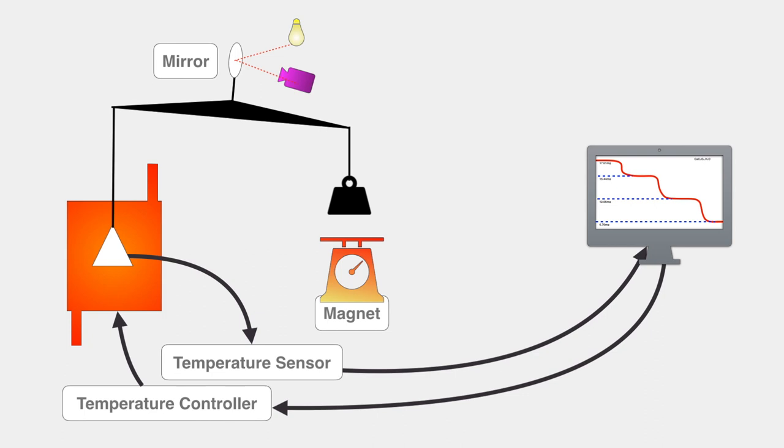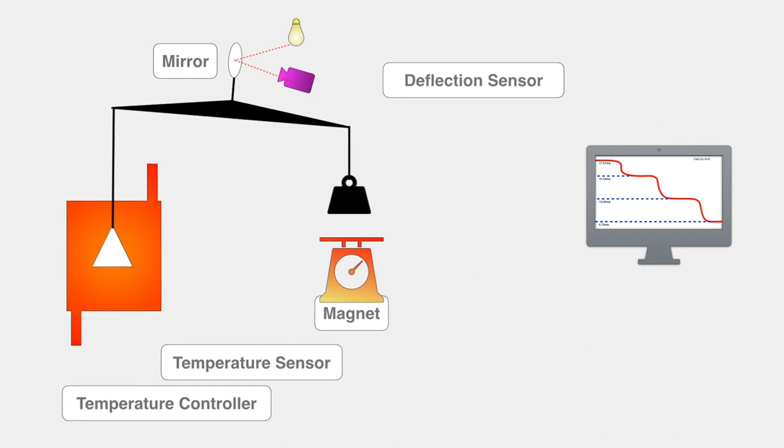During this movement, the mirror attached to the balance reflects the light at a certain angle. This deflection in light beam is recorded by the computer and the computer again sends the required amount of the current to the magnet so that the reference weight is again pushed upward and mirror is moved to its horizontal position.